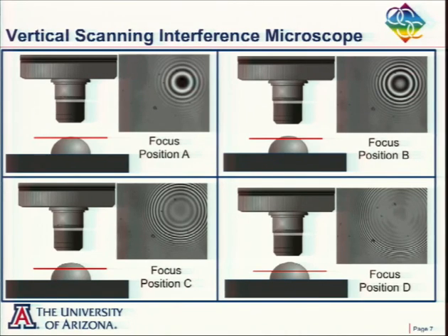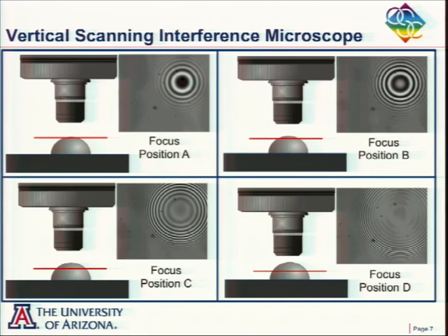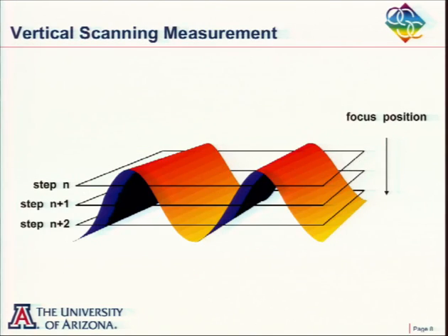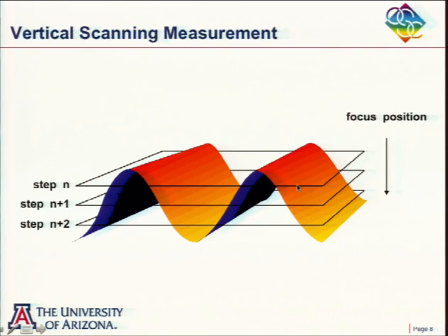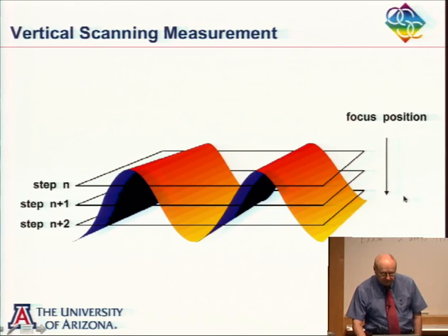This is nothing Michelson didn't know, but he didn't have the computing power to go through this vertical scan and measure the contrast point by point, calculating where the maximum contrast is as a function of scan position. We're measuring a layer at a time as we do the scan, looking at the contrast over a million points plane by plane as we move along — perhaps an eighth of a wave between measurements, well under the quarter-wave requirement.